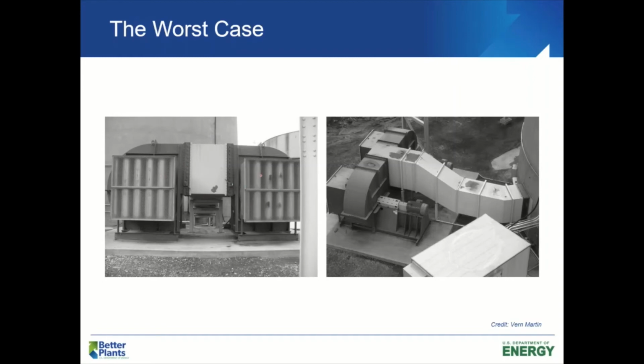If one's not working and the other one is, it's literally just trying to spin that other fan backwards, okay? Because not much of the air is being directed and pushed into the stack or the column, right? They're just constantly battling one another. So this is just a really poor initial design, right? And this is definitely a case where, as a manufacturer or as the end user, you're not getting anywhere near the rated value of what those fans can provide. And it's not due to the fan's fault, it's just poor installation, okay?